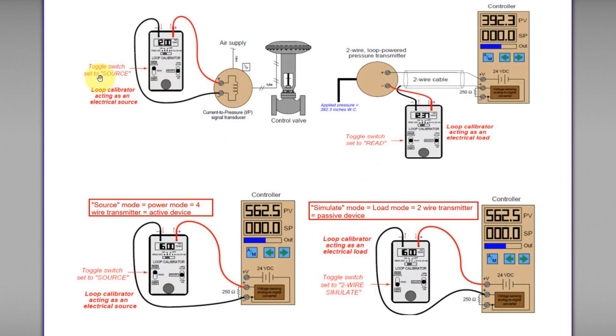Source mode is the mode that not only injects a signal but also provides the power to power the whole loop. Whereas simulate mode is just a mode that injects a signal to the loop; however, it does not provide the power to power the loop.